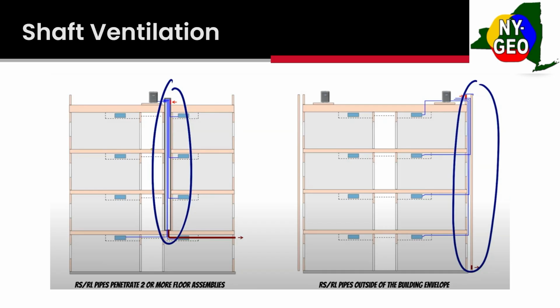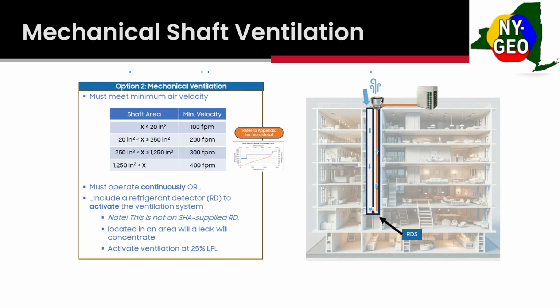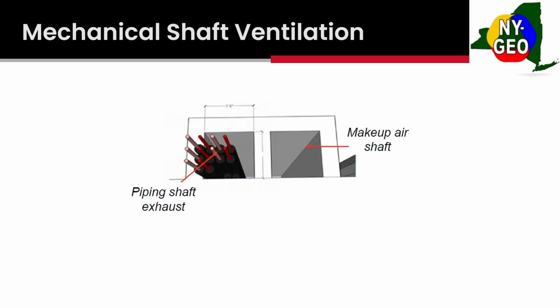So your mechanical ventilation requires a little more work to design. So you've got minimum air velocities you have to keep, depending on the shaft volume. You're going to have an exhaust shaft and a makeup air shaft. The big thing with this is you're going to have an RDS at the bottom of the shaft, so if there is a refrigerant leak, it's going to pick it up. And your exhaust fan can operate continuously or based on when that RDS goes off. And it's going to go off at 25% of LFL. So here's a picture of what the top of the shaft would look like. On one side, you're going to have all your refrigerant piping and then your makeup air.